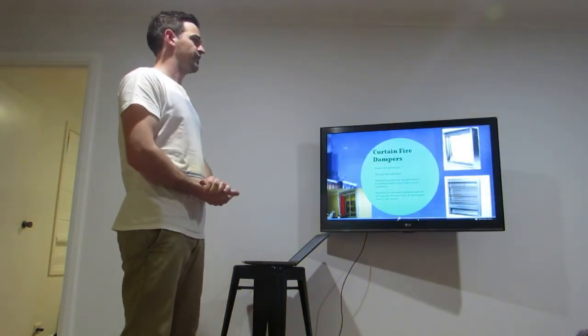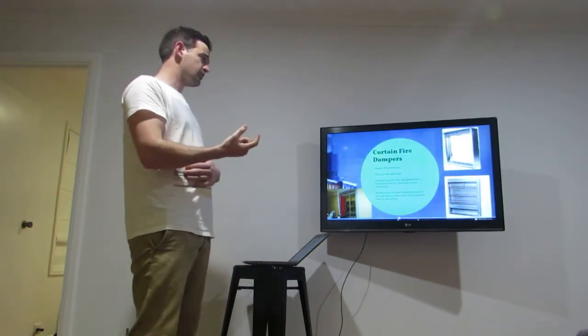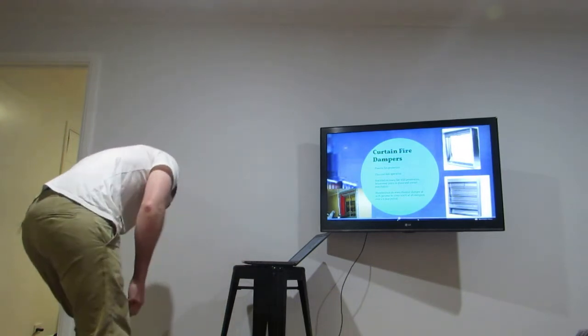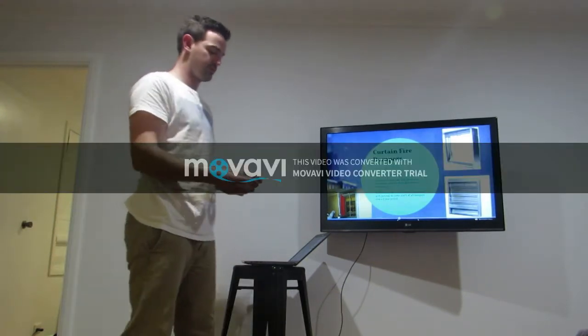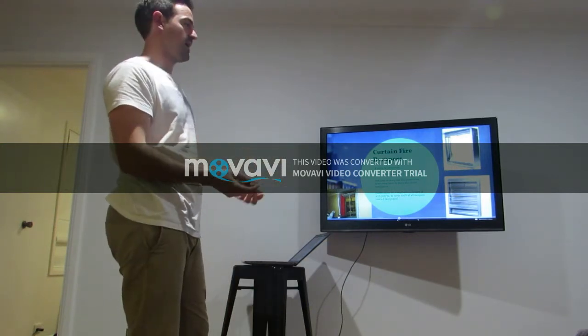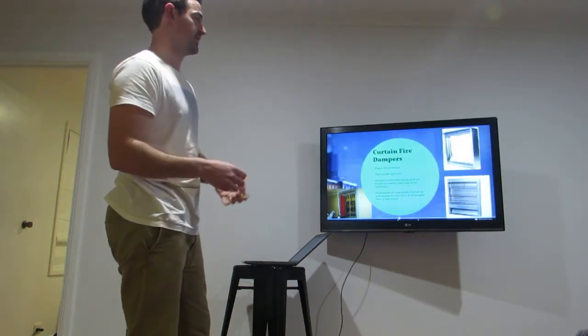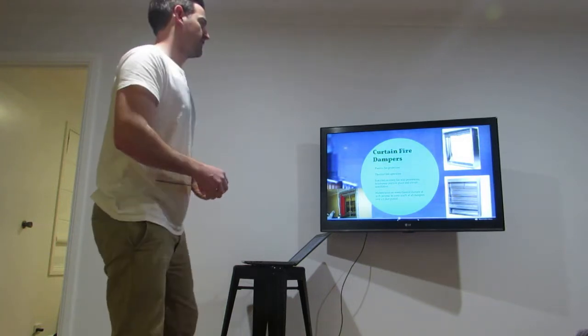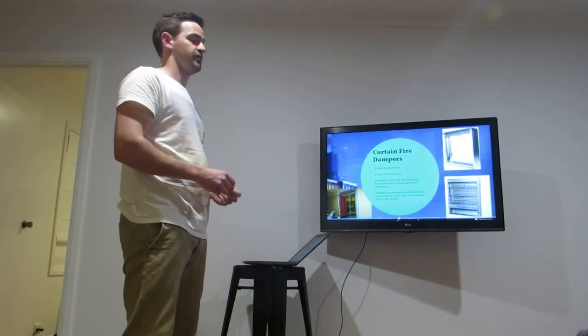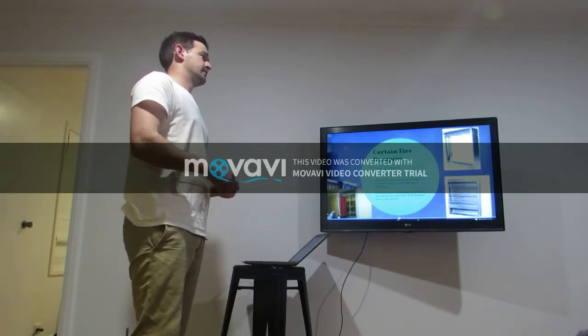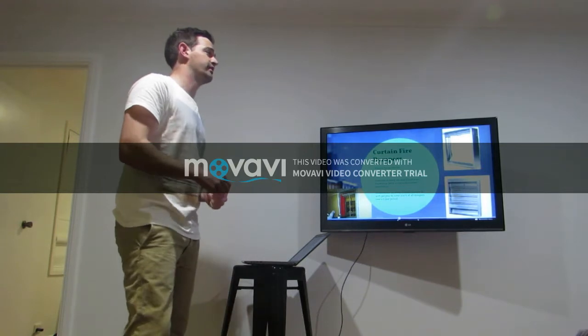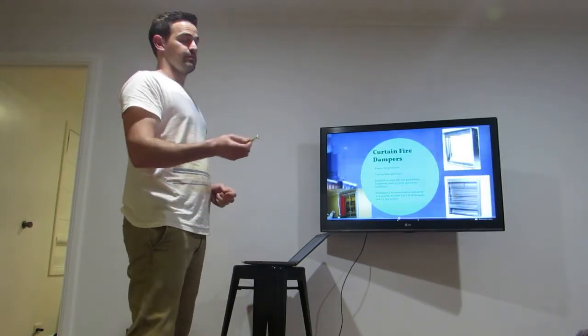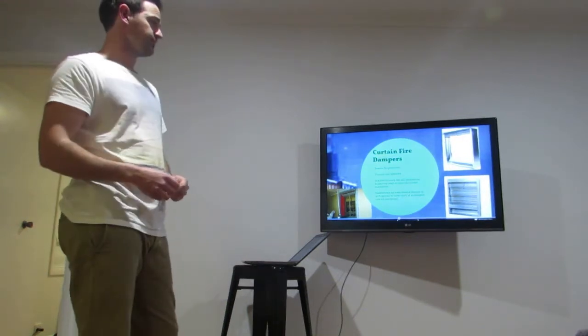Curtain fire dampers are the most commonly used damper in a multi-storey building. They have a shutter which can drop, released by a link breaking open. I have a couple of thermal links here. These have solder between two components, and once that solder melts they break apart, allowing the shutter to drop. These two are rated at 71 degrees and 68 degrees. Now these fire dampers are installed on every penetration on a firewall. Every single one of these needs to be checked. There's 20% per year to be covered and 100% over a 5-year period. The thermal links themselves need to be replaced every 25 years.